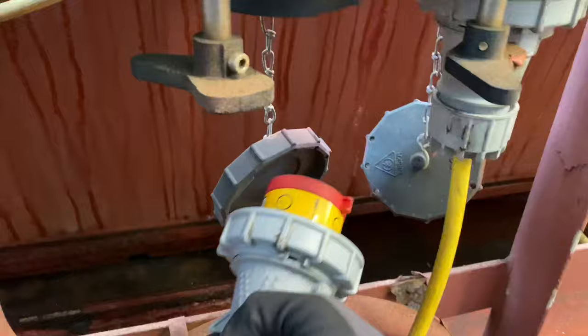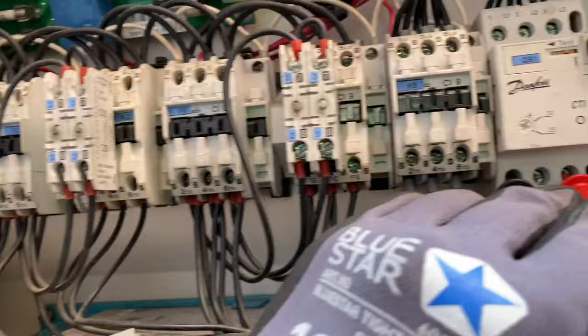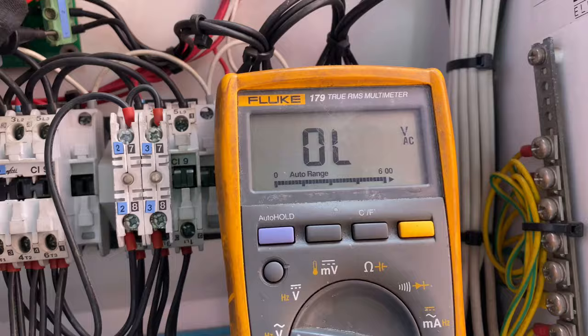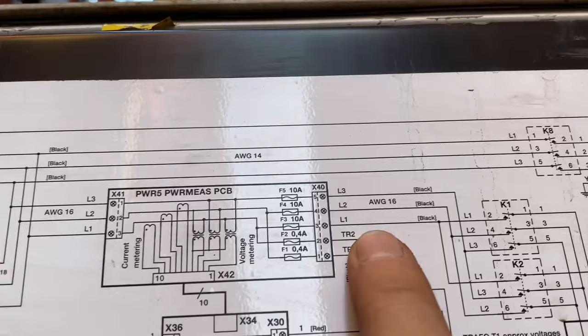The unit is giving an invalid power supply, so the first thing I did is to transfer the power plug to another reefer socket. After doing this, the voltage is still fluctuating on the controller reading. So I checked the supply voltage and it's giving me 450 volts. I then moved on to measuring the PWRMEAS PCB, getting 450 volts on its input and around 430 to 435 volts on its output.